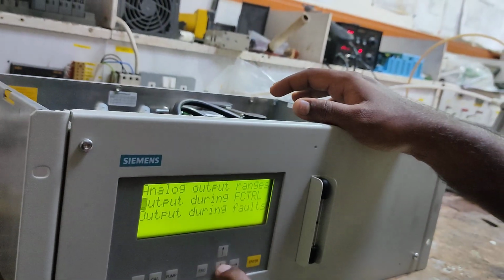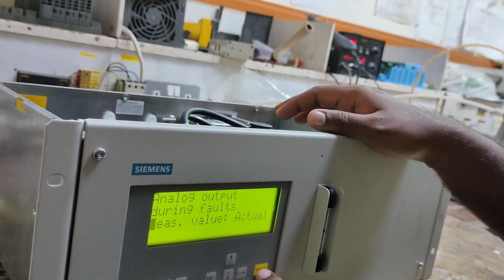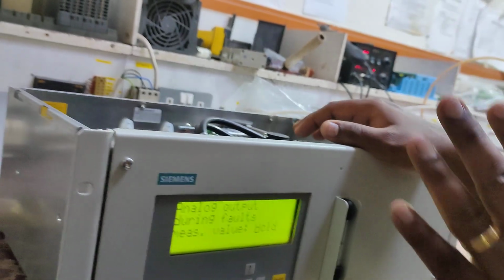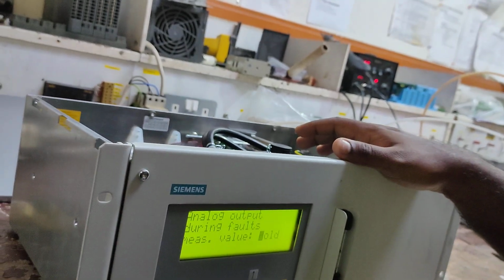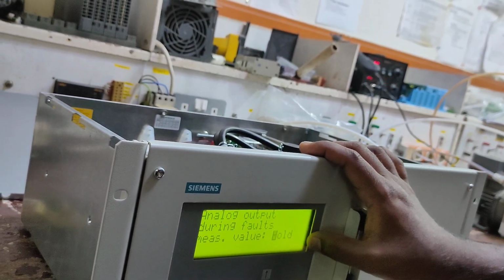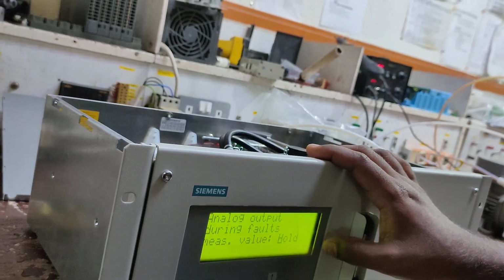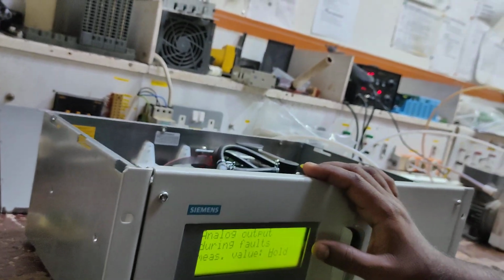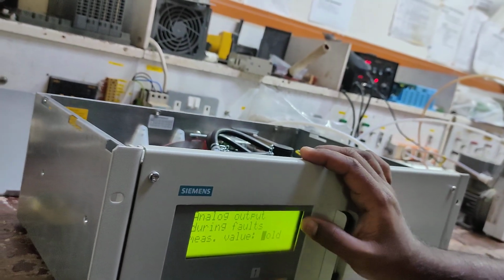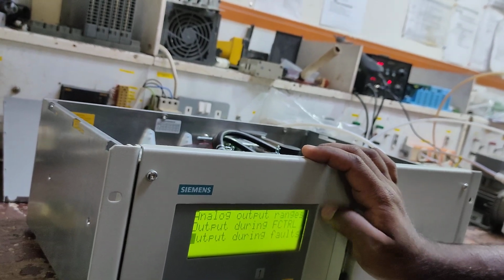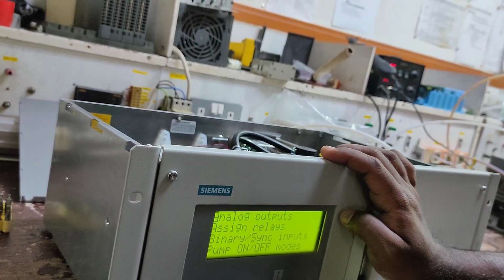Similarly, during fault, what should the value be? If you want to put it on hold, it will remain on hold at the last value. So this you have to decide. During the fault condition, what should the loop current be? You can decide from here. If it should be the last value which should hold, you have to select hold here. Presently, it is on actual.